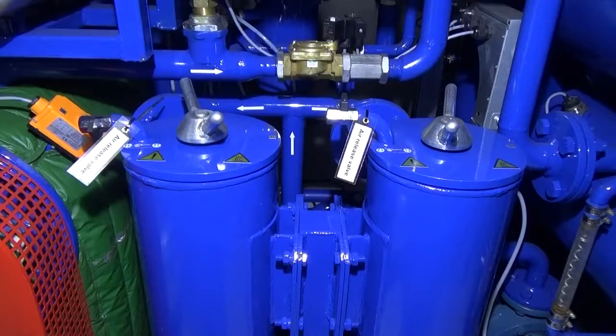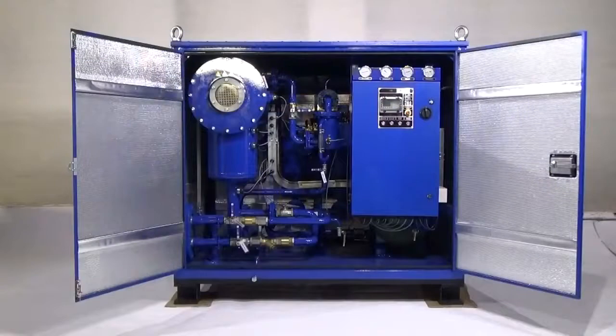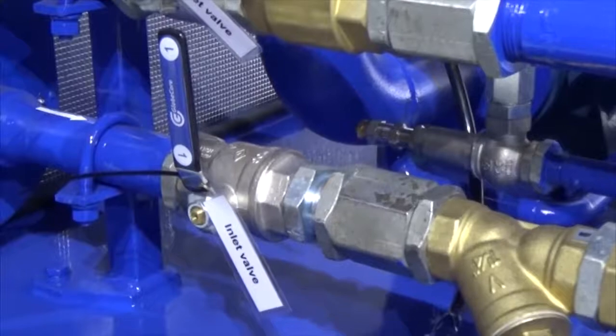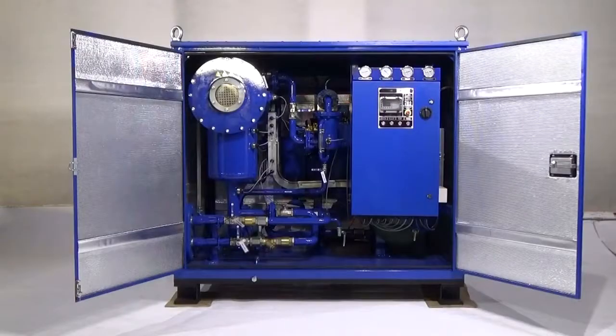7. Carefully and partially open air inlet valves MV11 and MV12 on the fine filters. Do not allow oil to splash out. After the filters are filled with oil, close valves MV11 and MV12. 8. When the oil level in the vacuum chamber reaches the mid-level sensor, close valve MV1. The light on the sensor shows that the sensor is engaged. 9. The unit will continue to operate automatically, circulating the oil inside.